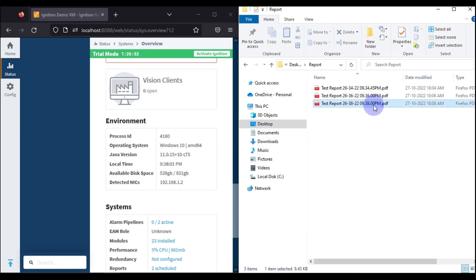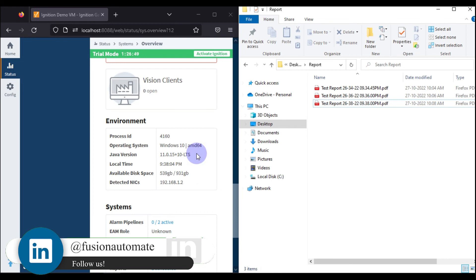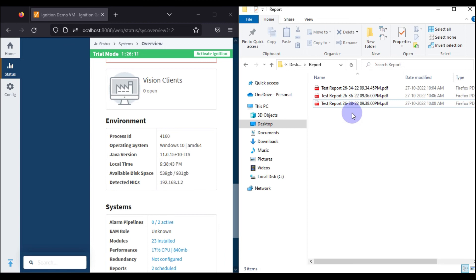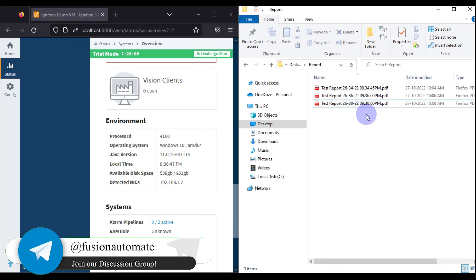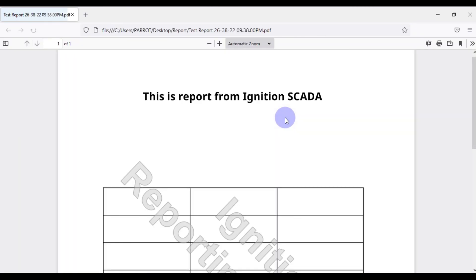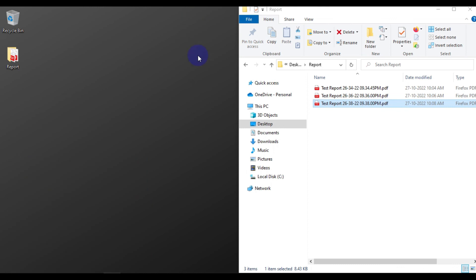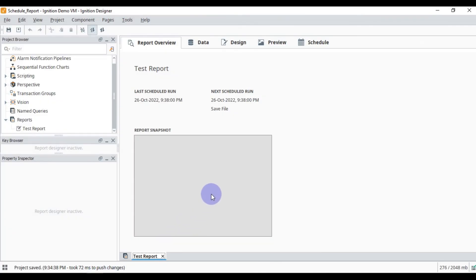It's 9:38 and our report is stored in our folder. Note that the gateway time is America/Los Angeles time (GMT-8) and my system time is Indian time, which is why there is a difference between the report name and the date modified. Our main focus was to see the report scheduler. We can save our report to the local machine using the Ignition SCADA report scheduler. If you open the report, you can see whatever we designed — 'This is report from Ignition SCADA' and our simple table.